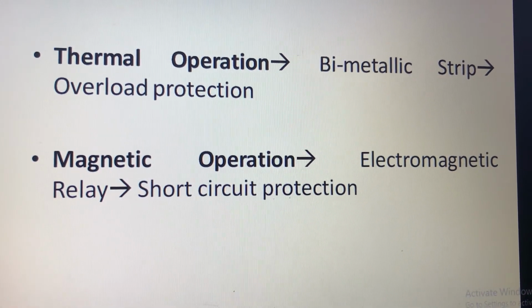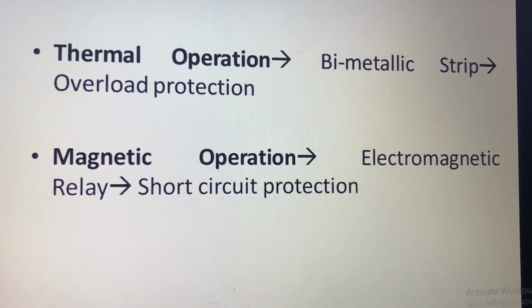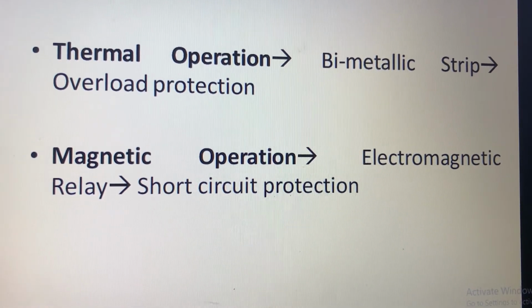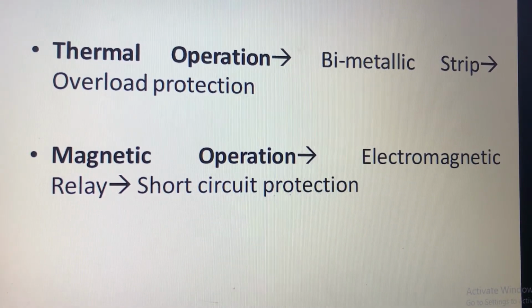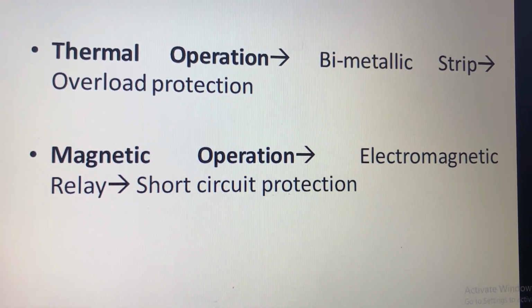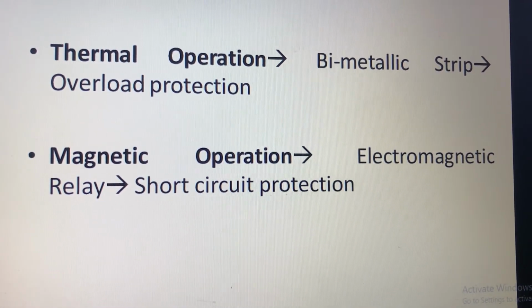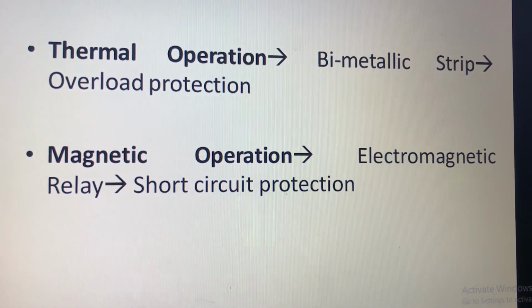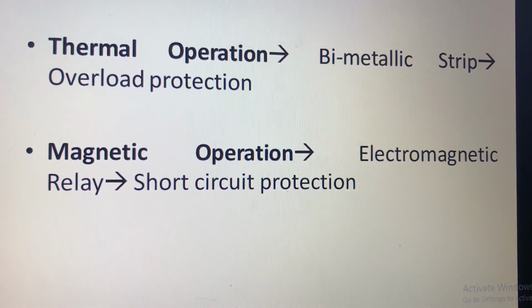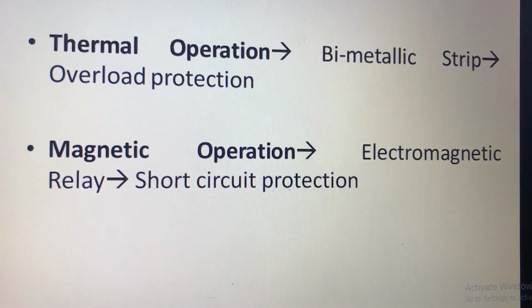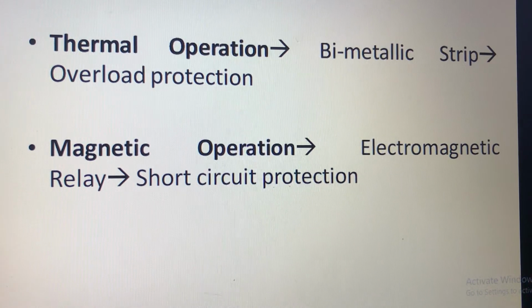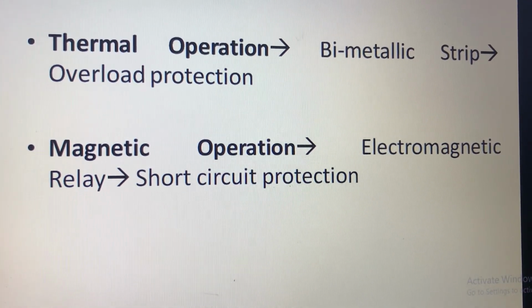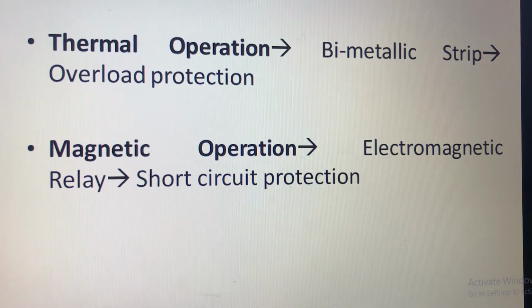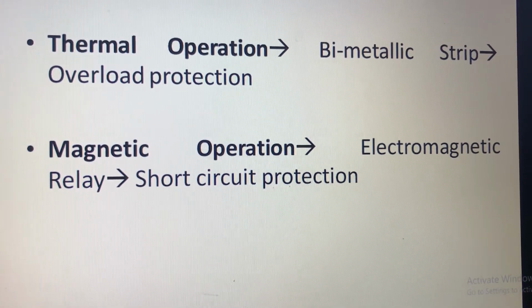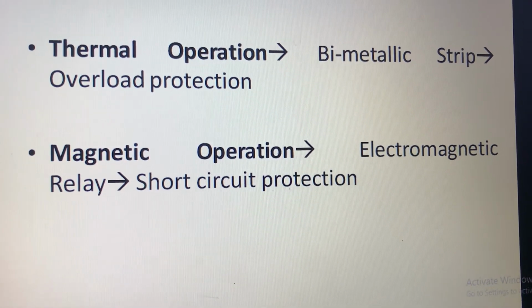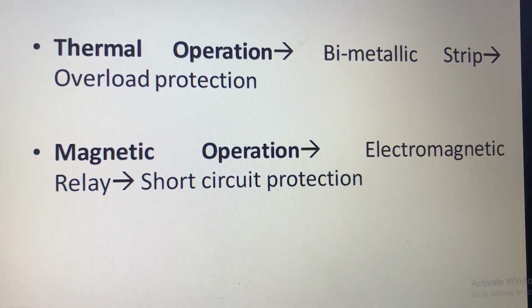Then is the magnetic operation. As we know, current is having magnetic effect. When current flows through the coil, it will make that coil a magnet. So the poles develop at the ends of that coil. So this effect of the current is used to provide short circuit protection in an MCB. So it is provided via electromagnetic relay, as we have seen in the diagram. So the two operations are thermal and magnetic. Thermal is for overloading protection and magnetic is for short circuit protection. Thermal effect of the current is used in bimetallic strip and magnetic effect of the current is used in electromagnetic relay.